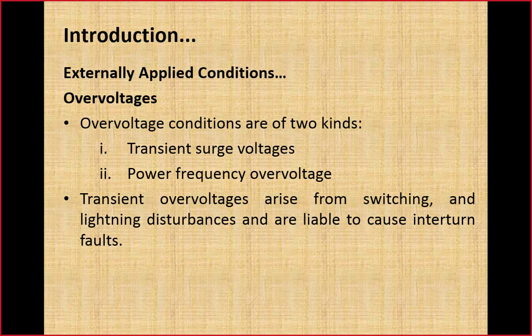Such type of protection is not provided to the distribution transformer on both sides. In case of distribution transformer, this protection is only limited to the high voltage side, and with the help of arcing horn, arcing rod across the bushing of the transformer, transformers are protected against the lightning transients.